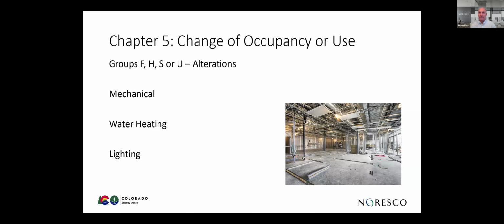For our domestic water heating, if your energy use is the same or increased, you are to follow the domestic water heating section, which is C404. However, C404 does not require commissioning. I think they goofed in that. I would suspect in the next code cycle that changes. But for now, in the change of use or change of occupancy, domestic water heating would not need to be commissioned. Lighting. If energy use is the same or increased, it needs to be commissioned. Pretty simple. And that's it for change of use or change of occupancy.